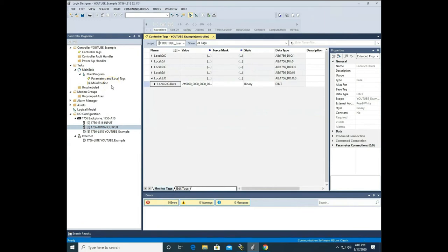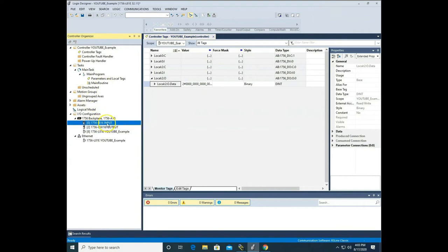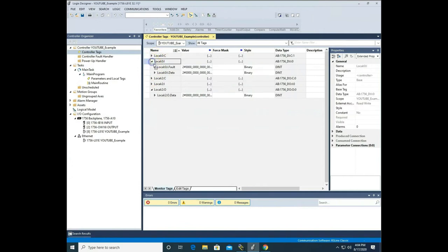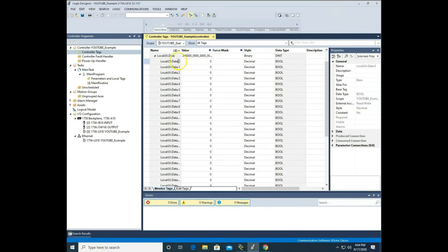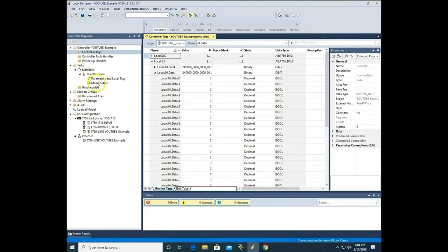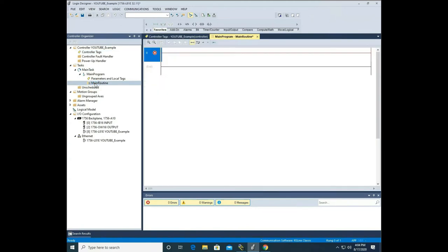Let's create a simple program where if we push a push button, we turn a light on. We have a push button wired to input channel 0 and a light connected to output card channel 0 — whenever that push button is pushed, we turn on the light. Remember with Allen-Bradley: your slots start with 0 and so do your channels. Notice our local 0 input starts with channel 0. So let's go into our main routine and double-click it — this is where we program using ladder logic.